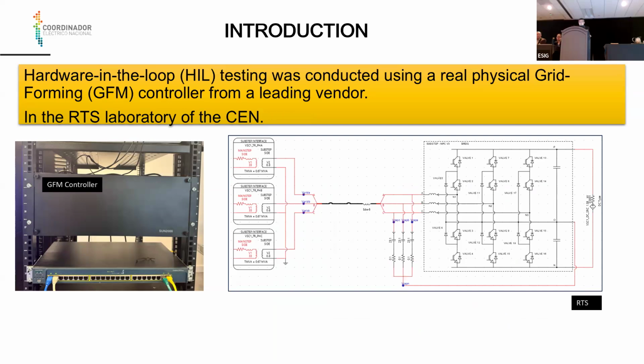At the time of the requirement formulation, we had just one grid forming controller. Right now we have two, so we are retesting the typical tests for grid forming capabilities, but with two grid forming controllers. We do that in our RTS laboratory.